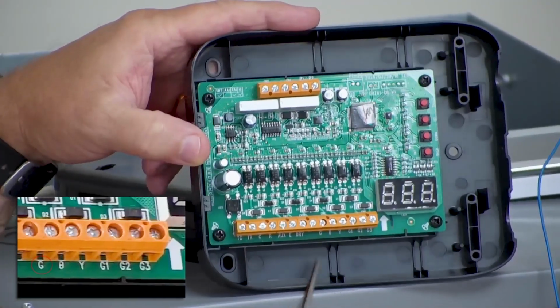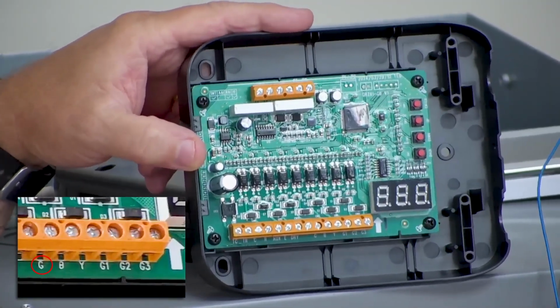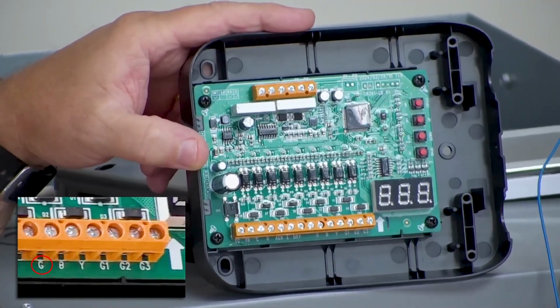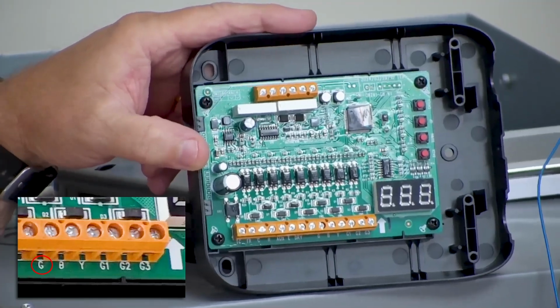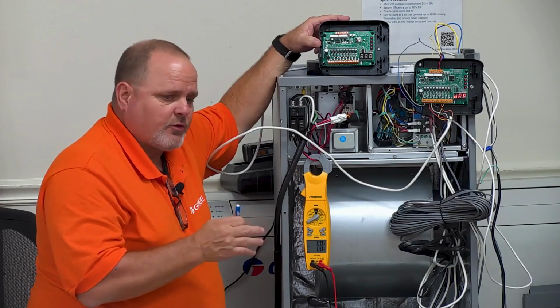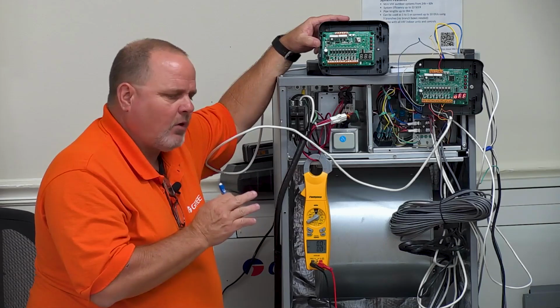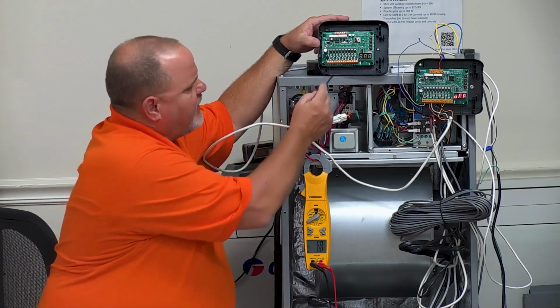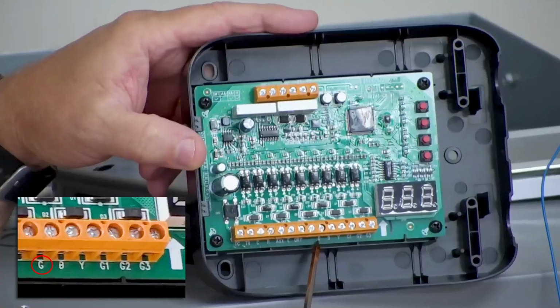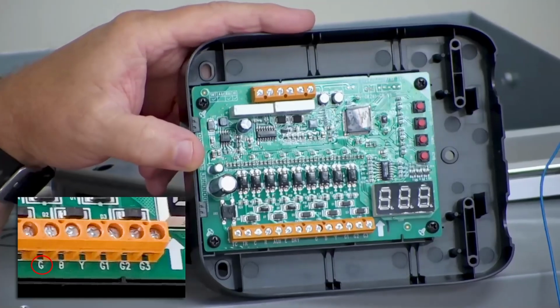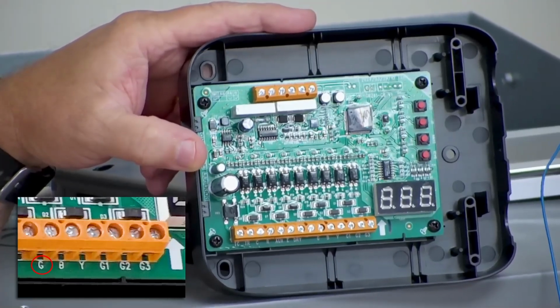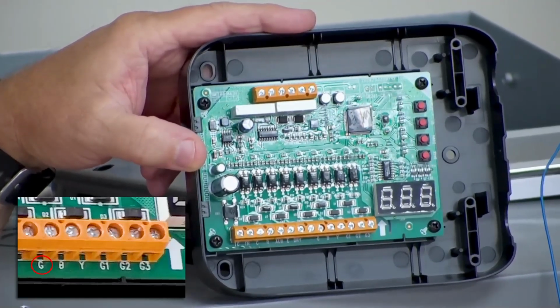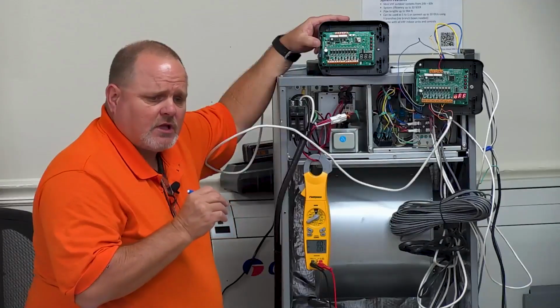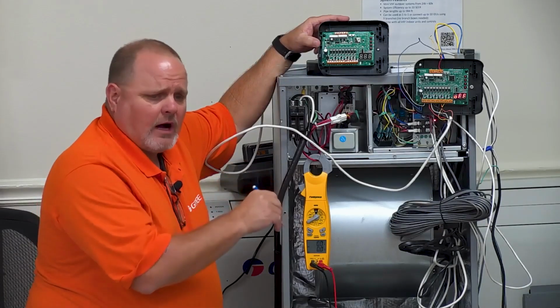Your G call, so you can do a simple G call. Most thermostats only have a G. Most of them don't have G1, G2, G3. This gives you the ability for both, and I'll go into more depth on that. But if you use the G terminal, there's a P code on it you can set to determine what blower speed you want it to run at when it gets that G call. So you can actually select from low, medium, or high.